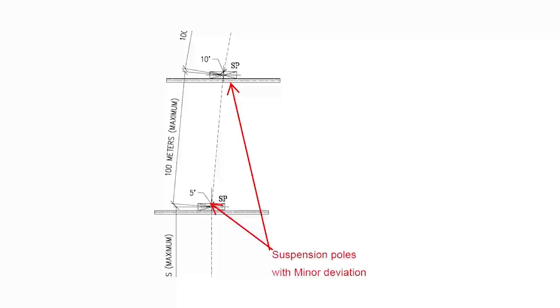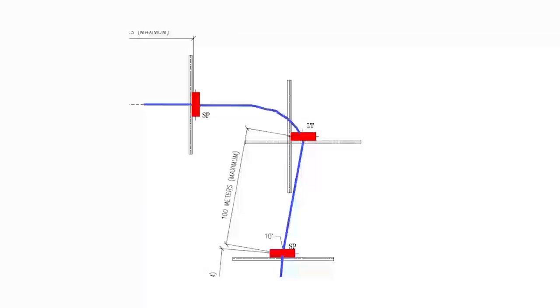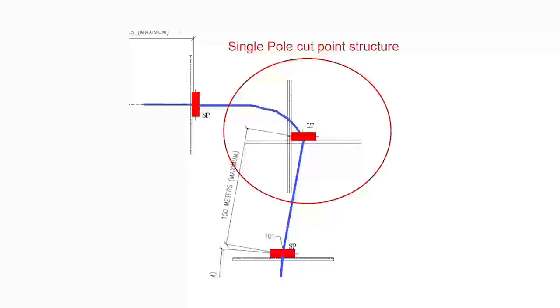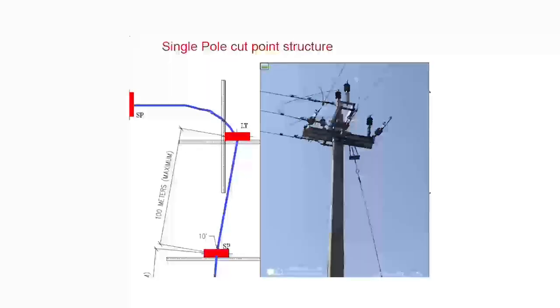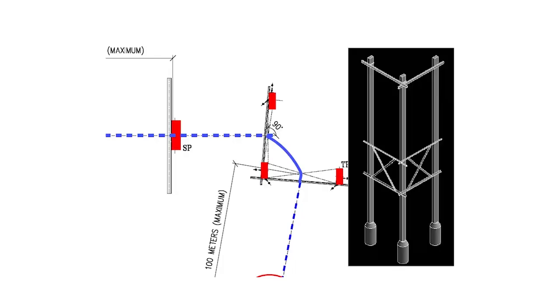When the angle of deviation is more, then we go for a cut point as shown in the figure. After this, we have a single pole cut point wherein it takes a 90 degrees turn. In this place, we use two structures which are perpendicular to each other as shown in the drawing, and as shown in the photograph, you have a cut point using a single pole. Next, we will see what happens when we go for 90 degrees if a single pole is not being used.